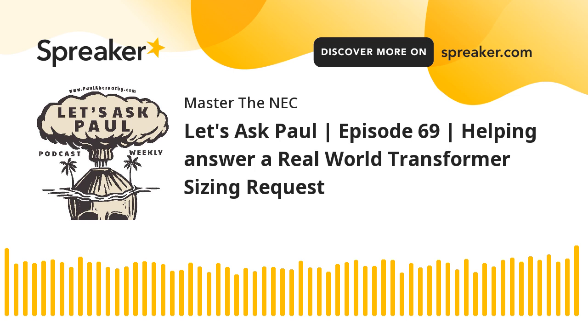It says the disconnecting means shall be lockable open in accordance with 110.25, and its location shall be field marked on the transformer. So on this transformer, you put a phenolic label. Obviously, it's got to withstand the conditions of use. Can't be just like an inkjet. You get the picture. And it will tell you where your disconnecting means is.